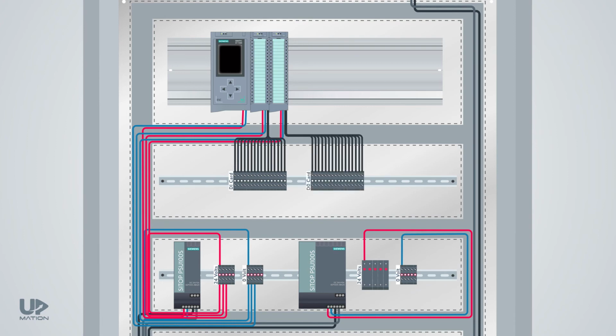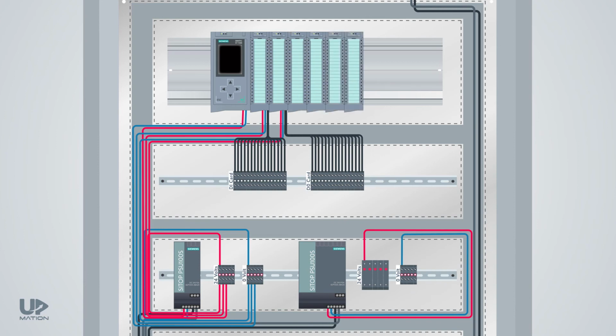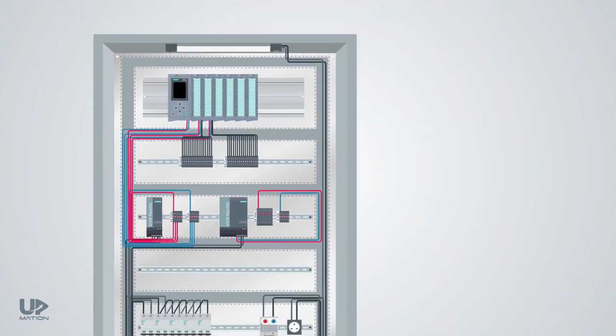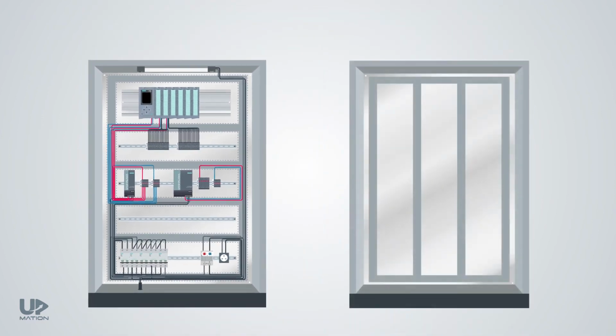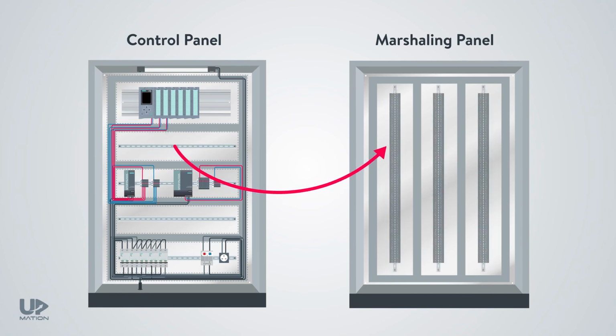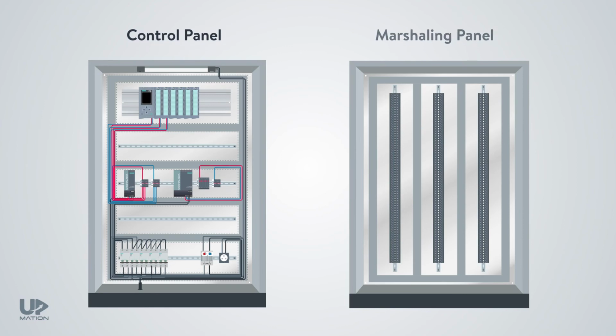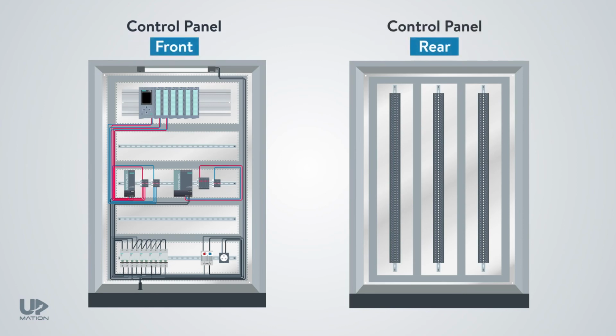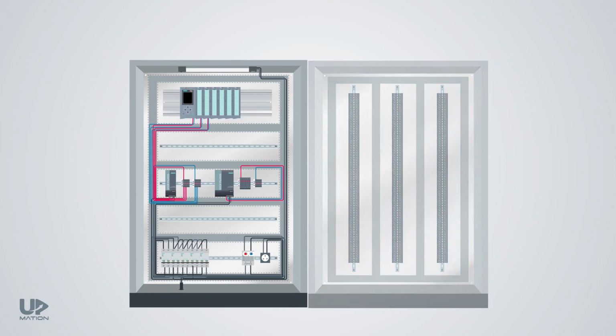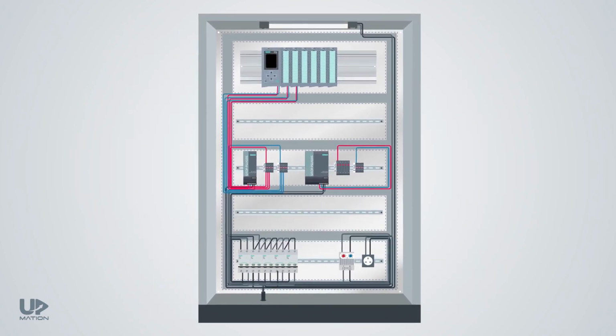You might be wondering, when we have more DI or DO cards, we'll be in lack of space for all of the terminal blocks. It is true, of course. If we have a huge number of inputs and outputs in the process, the layout of the panel gets completely different from what you see here. There should be another panel, known as the marshalling panel. In this way, we'll transfer all of these terminal blocks to the marshalling cabinet. In some enclosures, the rear section of the mounting frame can be used as the marshalling part of the panel, so that we can merge the control and marshalling panels and save lots of space in the electrical or control room.